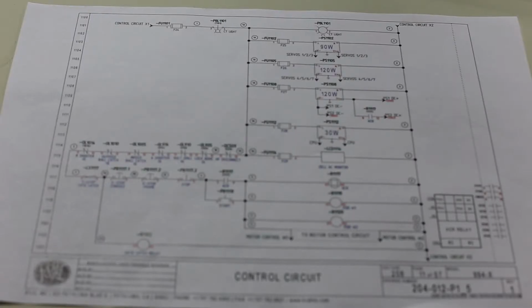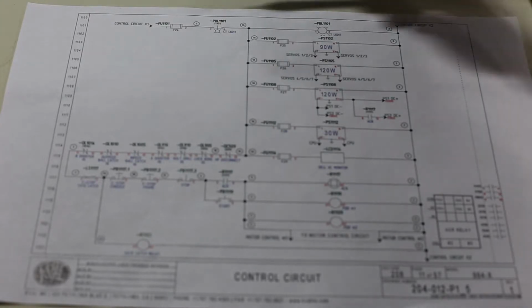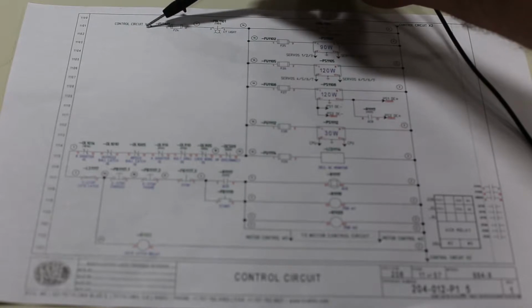When you're troubleshooting the control circuit of any of our Kval machines, they're all basically the same circuit. We start up here at the very top at the control circuit. That's where the control transformer is. This is the primary side, and we go through the transformer, and then we come out, and this is the fuse on the secondary side of the control transformer.